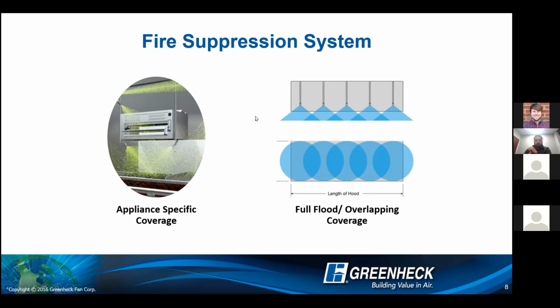The next reason you would use an overlapping system is if it's required by a local jurisdiction or by a specific building. Again, using a very specific example, in Bloomington, Minnesota, we have the Mall of America. And the Mall of America has just stated that it's going to have an overlapping fire system. And that's just going, if you're putting a type 1 hood in there, you're going to have an overlapping system.